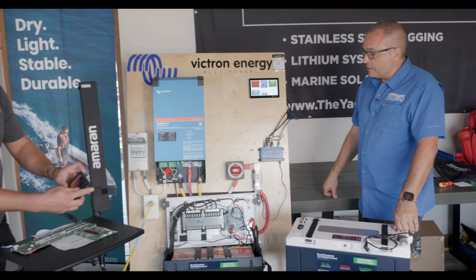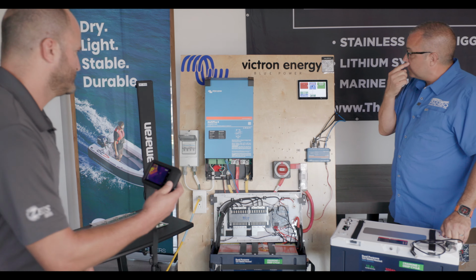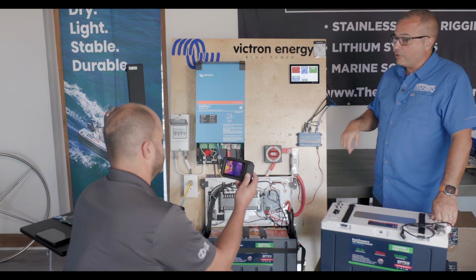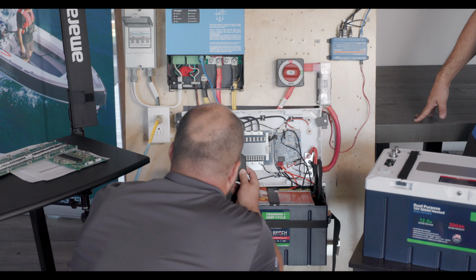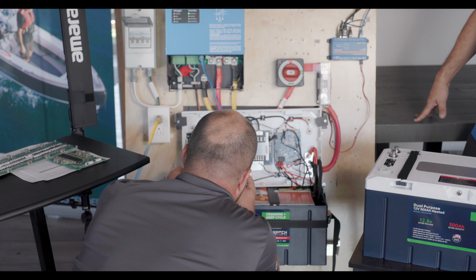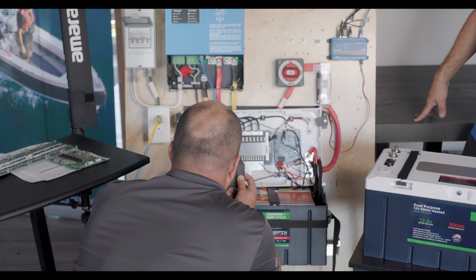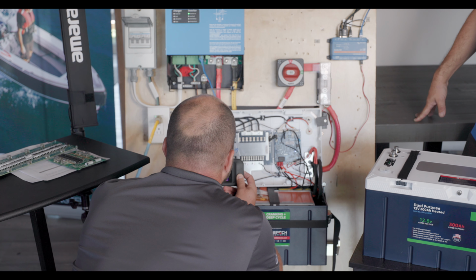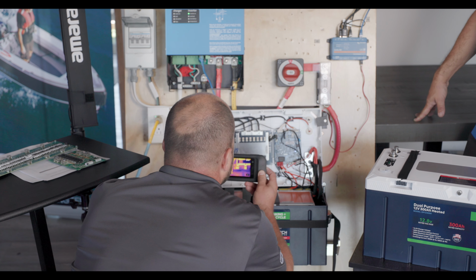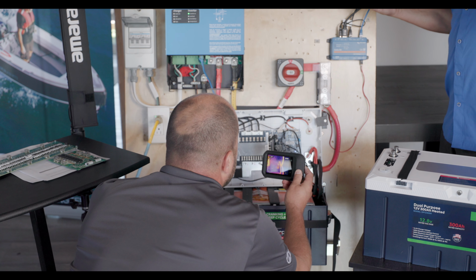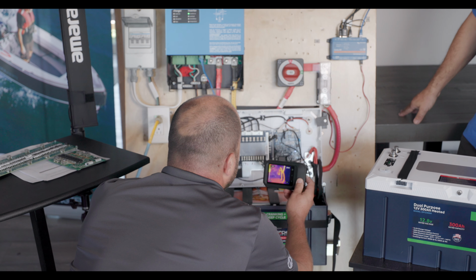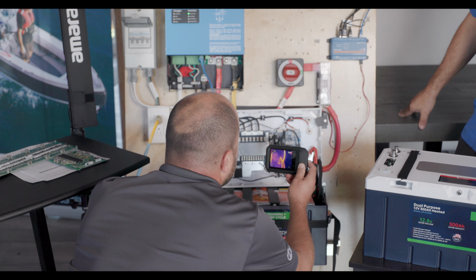Let's take a look at some of the temperatures. We've got 180 amps coming out of the battery, and we have for quite some time. So what are our hottest points? We're at about 116 on the board, 116 on the negative terminals, and 94 on the bus bar. It's probably 75 degrees in this room, so we're not all that much over ambient temp there.